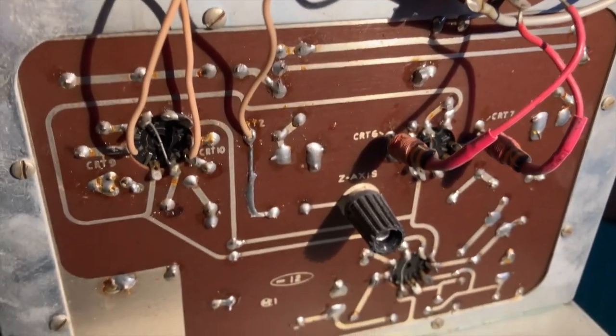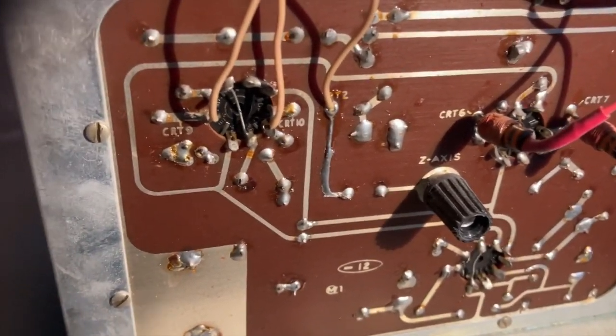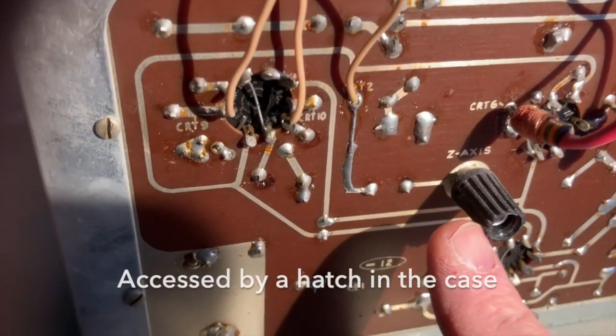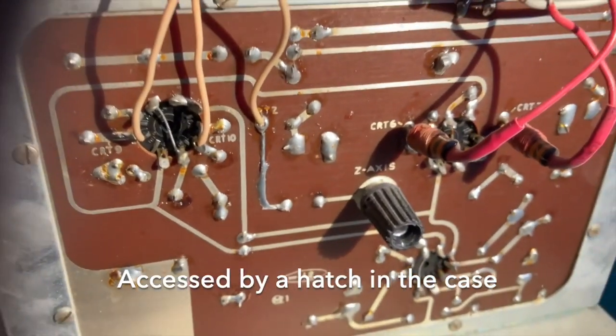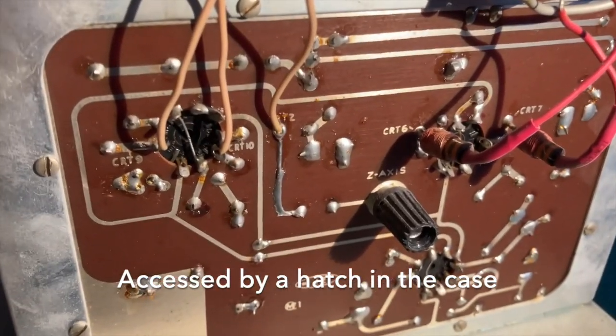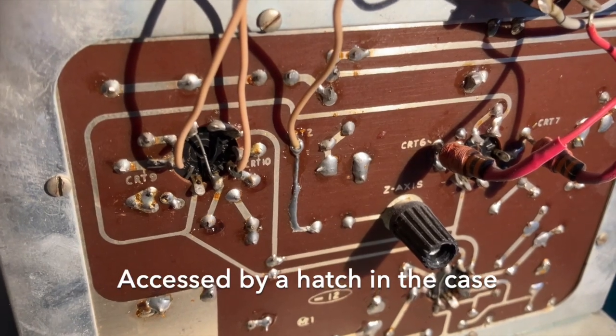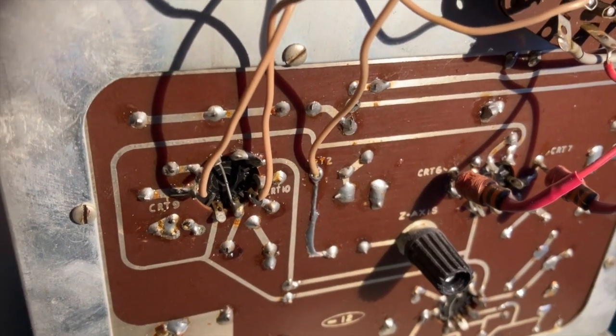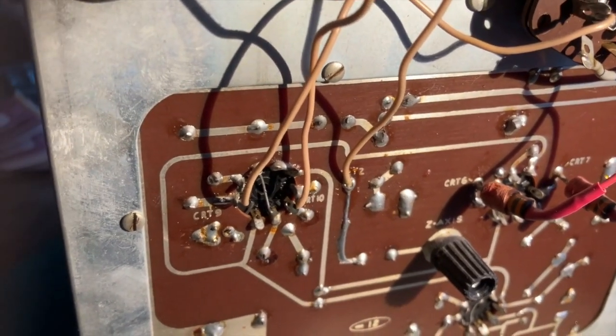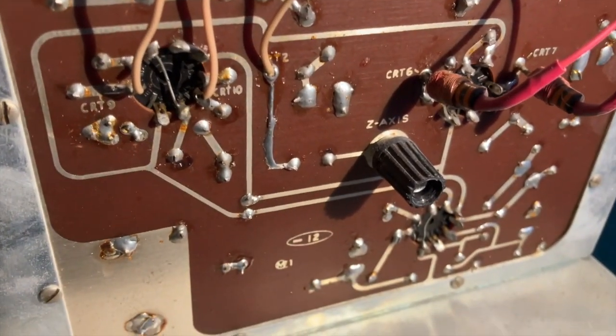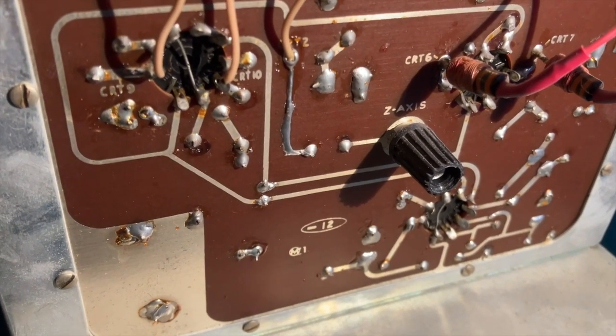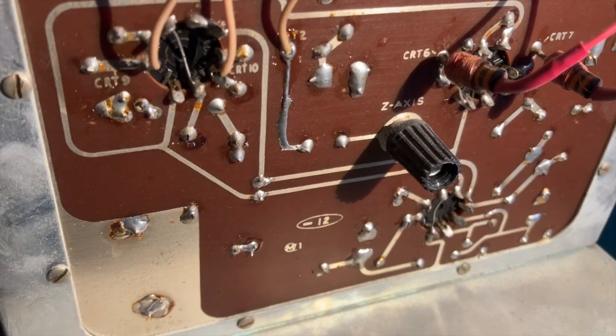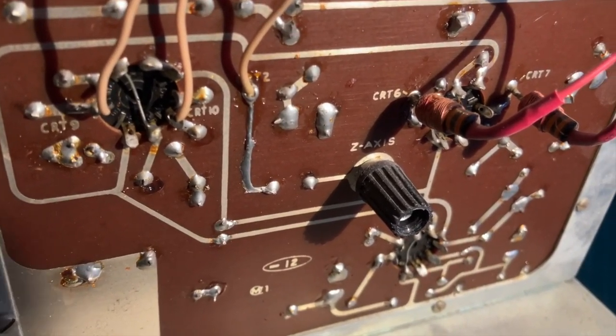Apart from that, on the back side of the circuit board, most prominently, we have a binding post for the Z-axis. This is where you can connect an external blanking signal if you wish. So if you're using the scope in XY mode, basically you can feed a blanking signal in here to modulate the CRT intensity, or turn it off, I suppose.